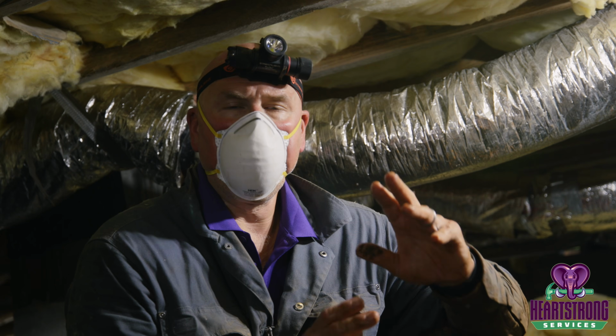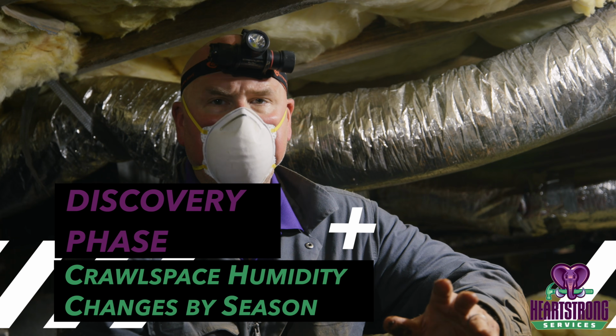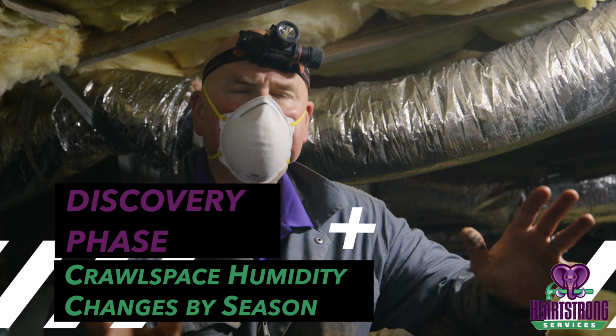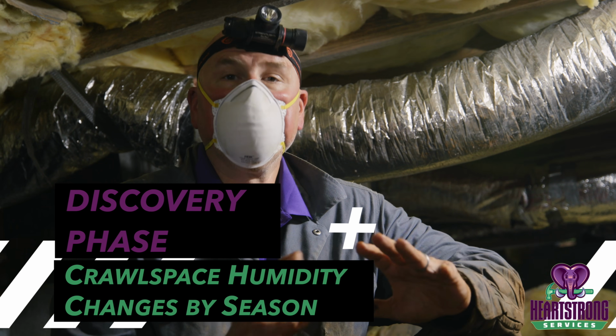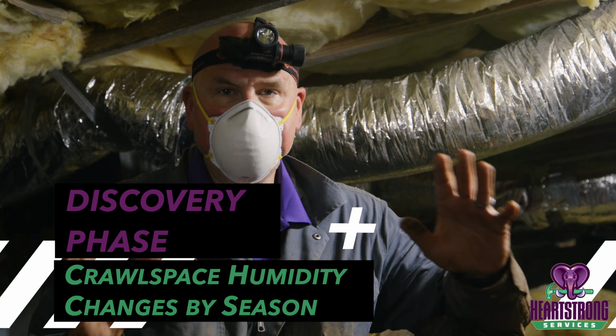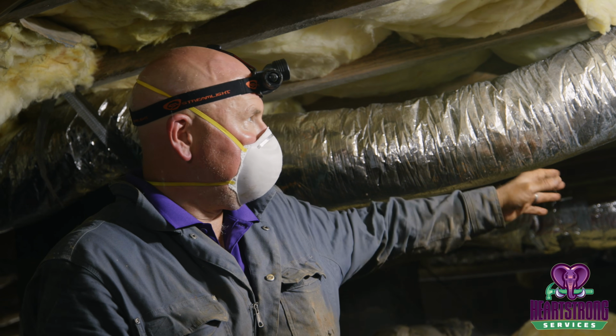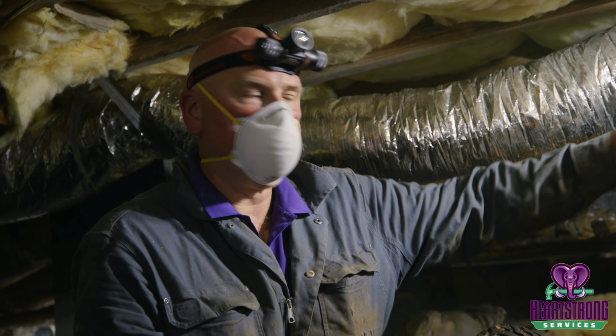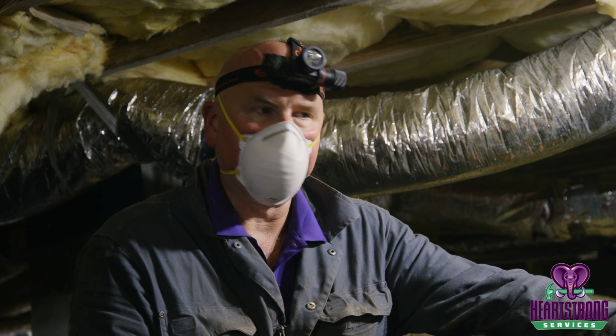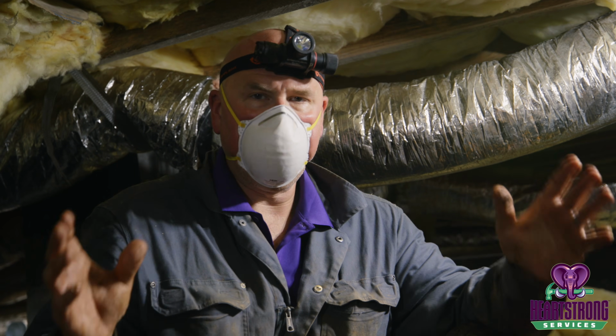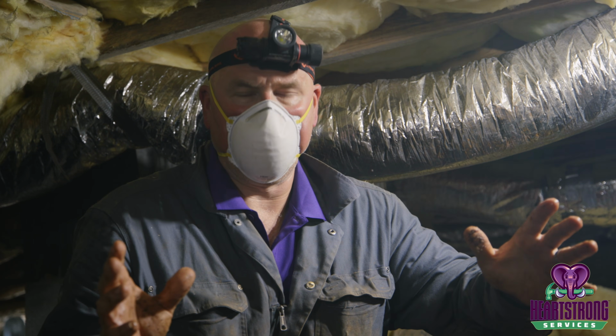All right, the other thing we want to be sure we're educating our customers on is this is a pretty typical crawl space you're going to see during the summer months here in the Tennessee Valley. And the reason we say that, we're talking about the amount of sweating ductwork and condensation. We got water pooling from the ductwork down here. We got high signs of humidity, high signs of wood moisture content.